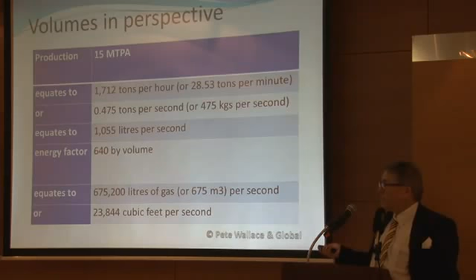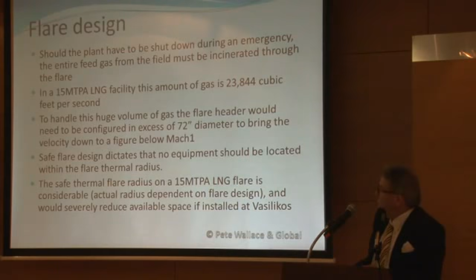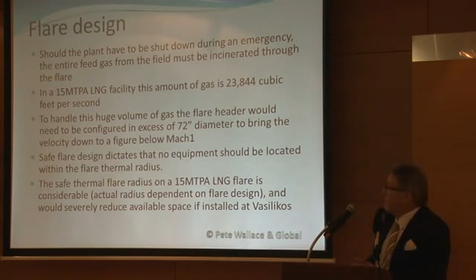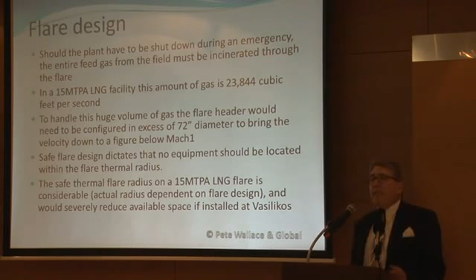Now, the flare size for a 15 MTPA plant is around about 23,800 cubic feet per second. This also leads to other problems, because should this have to go through the plant, this huge amount of gas needs to be stuck in a pipe of around about 72 inches. For one, the gas actually exceeds the speed of sound in it at that volume, so you've then got to split it up. The flare dictates that no equipment should be located within the thermal radius of the flare. And the safe thermal flare radius of a 15 million tonne per annum plant is in hundreds of metres. I can't give it to you exactly because it's totally dependent on how you design the flare.